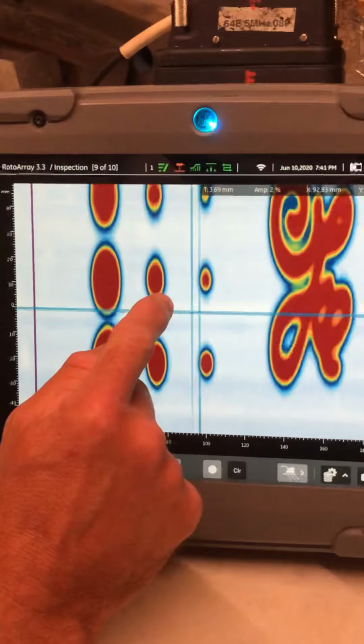So pop our roller on the part, just spray a little bit of water on there to wet the surface. We're going to hit the record button on our set and collect some data. So here we go. I'm a little bit offline, I'm not in the middle of it, but it doesn't matter for this.